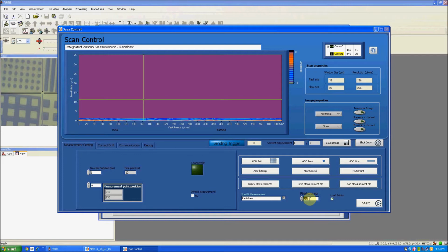So we have to decide on a number which makes sense. A typical laser spot is about 1 micron in diameter. So to get a good spatial resolution of the Raman from the laser, that means about half a micron. We have to make sure that our pixel setting gives us an acquisition about every half a micron. We have to remember we're doing AFM Raman here. We want to see a correlation between the AFM and the Raman. We're not looking to get a better Raman resolution. Better Raman resolution is TERS. This is not our scope right now.